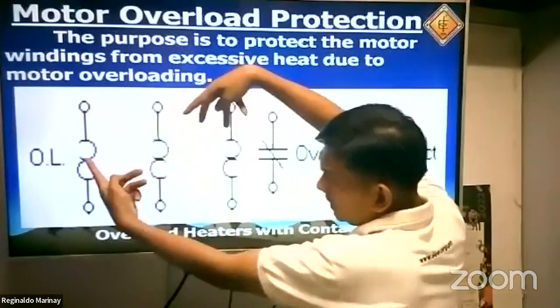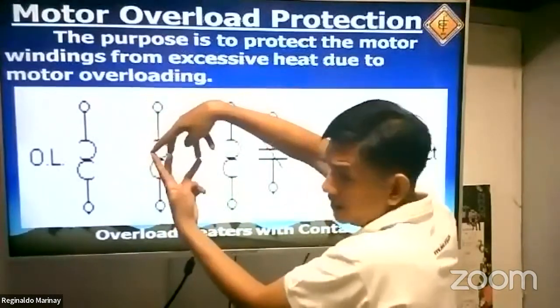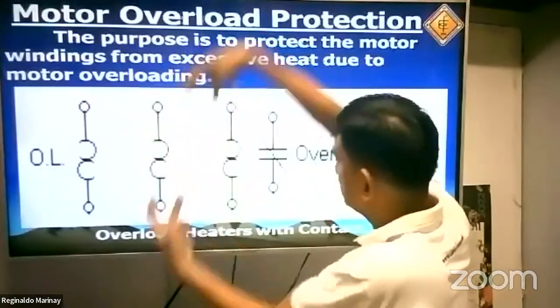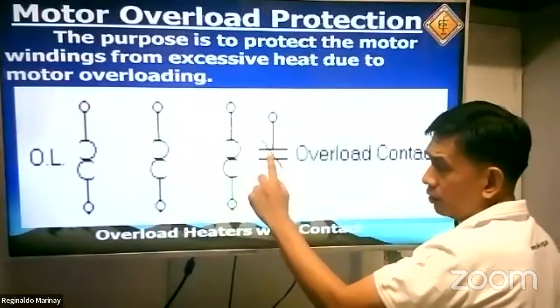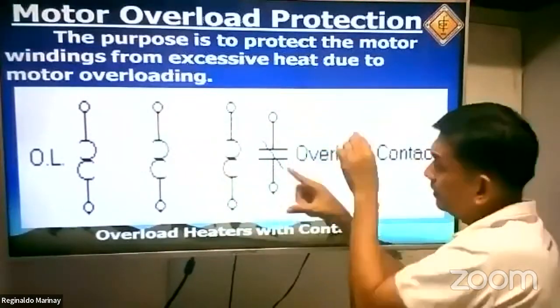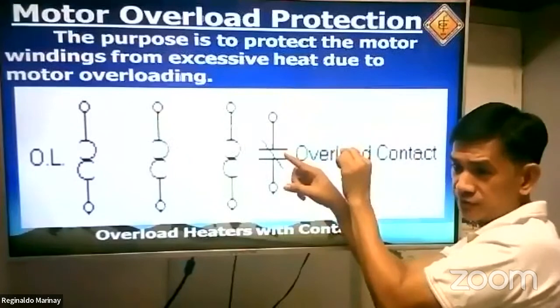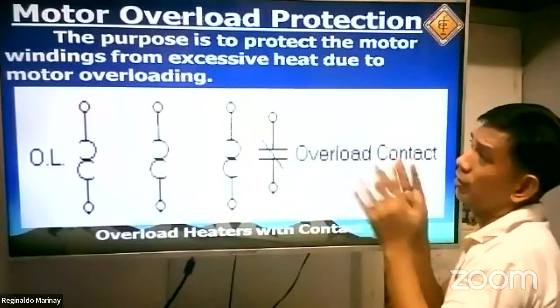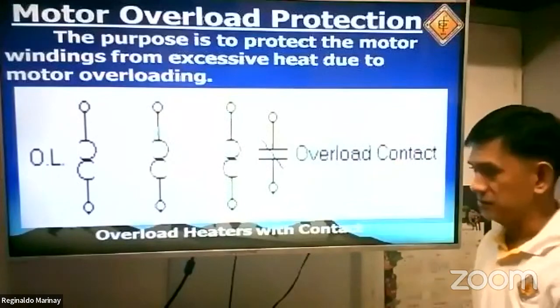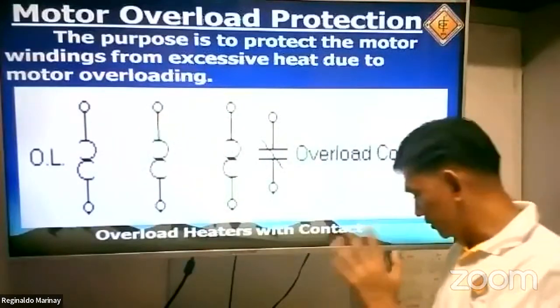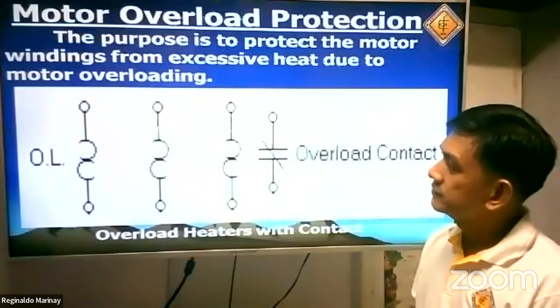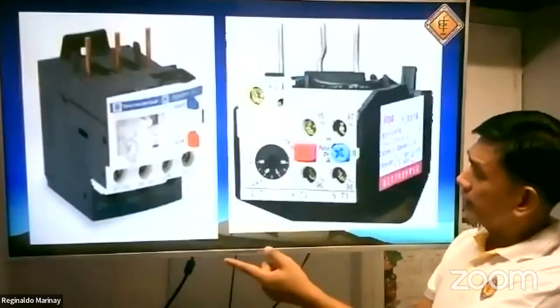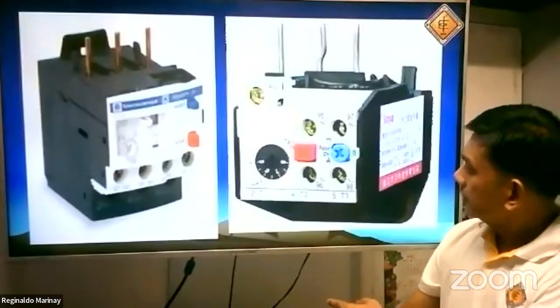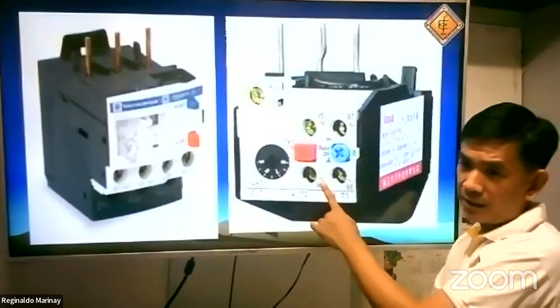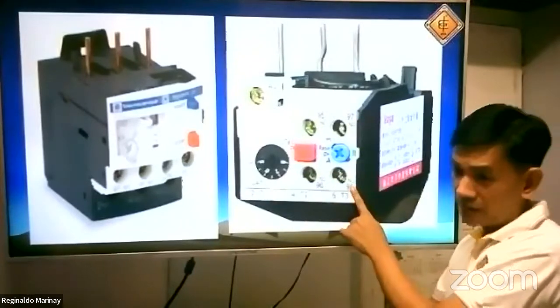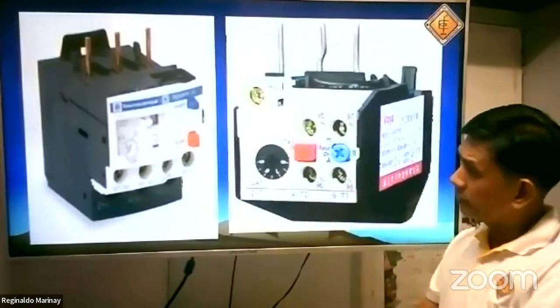Okay, simultaneously, the 3 contacts here will become open simultaneously, sabay-sabay. But once this becomes open, the normally closed will become open. And if there is normally open, that will become closed. Okay? That is the action of the overload relay. Okay? Or thermal overload relay. I think I discussed this in the part 1 already. This one. Okay. The 95 and 96 contact are normally closed. 97, 98 are standard normally open contact of the overload relay.